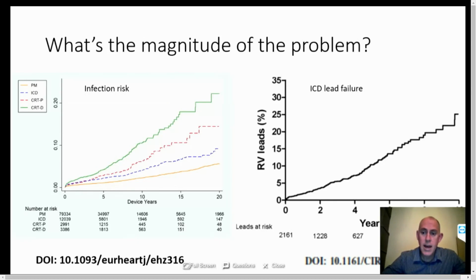So they have a failure rate associated not just with infection, but also with lead fracture at a much higher rate than pacing leads. And by the time you get out to more than 10 years, 25% of ICD leads have failed.